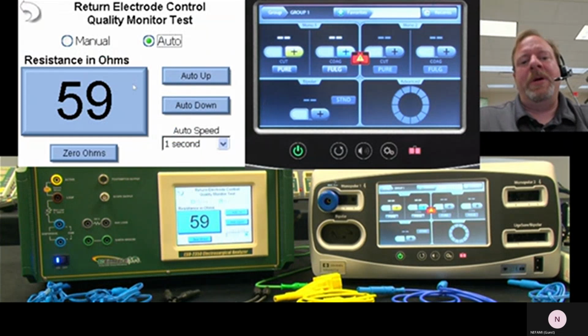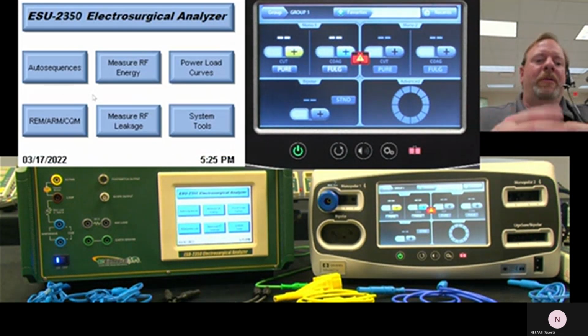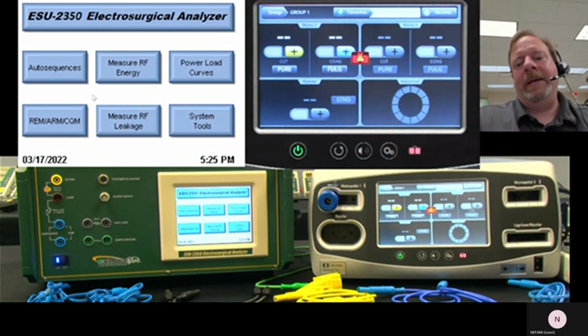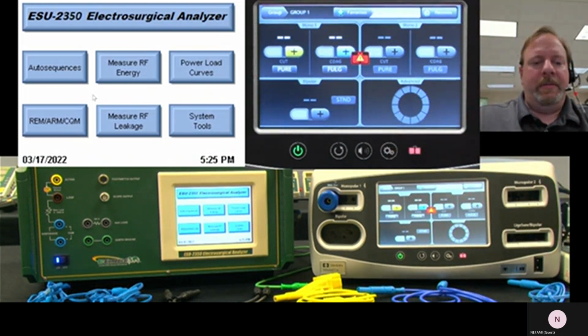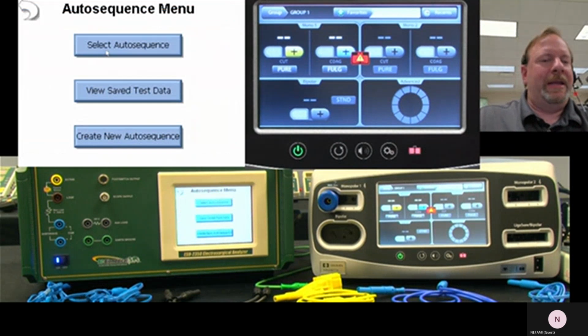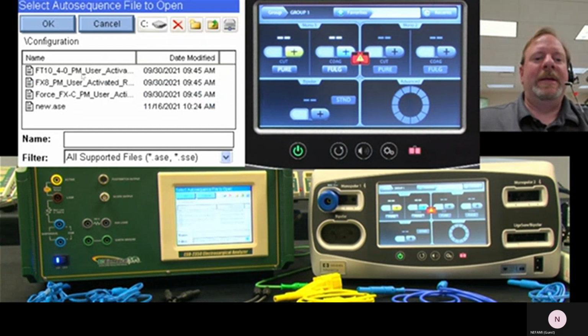We also have an automatic mode where it will just ramp up the output at this speed, and then you can stop it when your generator triggers an alarm. So that's kind of handy as well. Okay, so those are the main manual testing features. But the purpose of this demonstration here, the main meat here, is how do we do the PM procedure? So if you've been involved in that, it can be pretty lengthy through the service manual.